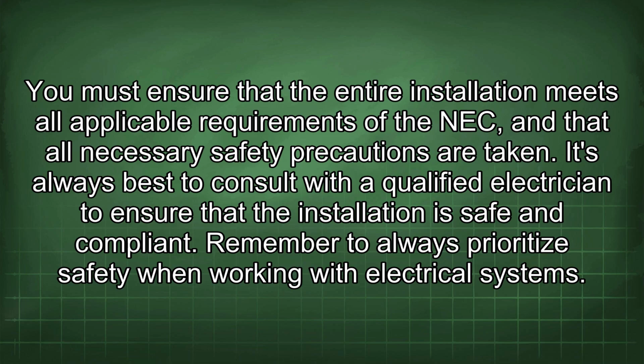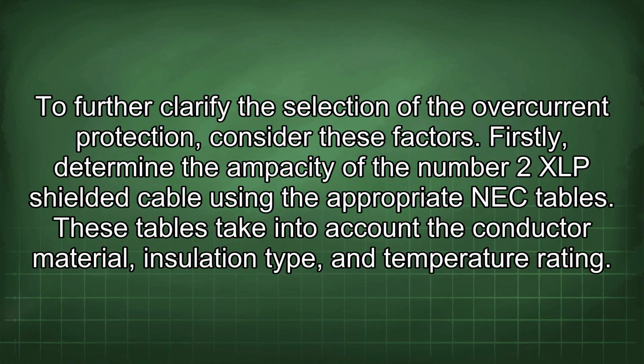Remember to always prioritize safety when working with electrical systems. To further clarify the selection of the overcurrent protection, consider these factors. Firstly, determine the ampacity of the number 2 XLP shielded cable using the appropriate NEC tables. These tables take into account the conductor material, insulation type, and temperature rating.